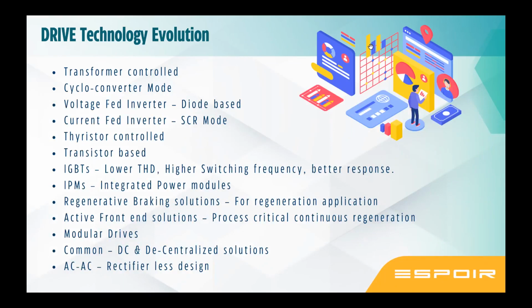So if you see the way the drives have been introduced in the market from the 60s, primarily it used to be a very, very large system, transformer-based control, then a cycloconverter method. Then two parallel technologies came, a voltage fed and a current fed type. Then thyristors came, then transistors, UJTs came in. Until the introduction of IGBT-based technology, it changed a lot, because in the IGBT, THD is very low, with higher switching frequency and better response. These are the reasons IGBT has dominated for the last 25 years.